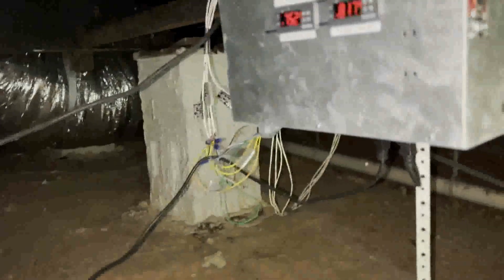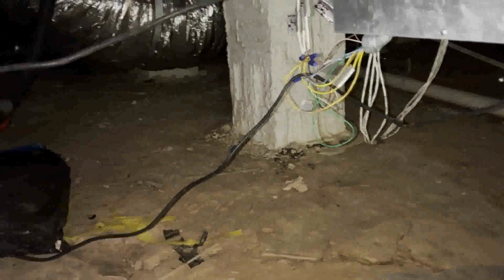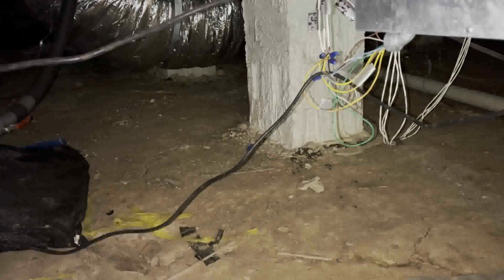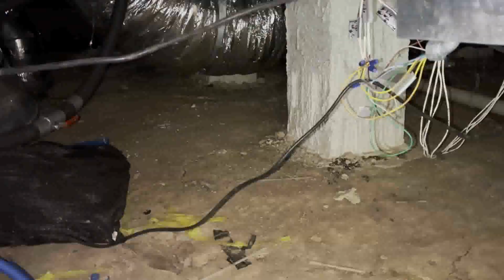So if that water temperature gets that low, that's happening because the heat's on and someone's taking a shower at the same time. So what happens if the water hits that low limit? It actually closes the house heat valve. Now I have a heat pump system. It works great. So if this condition happens where someone's taking a shower and the heat's on at the same time, that return water temperature is just going to start bottoming out. So it will actually close off the hot water to the heat.